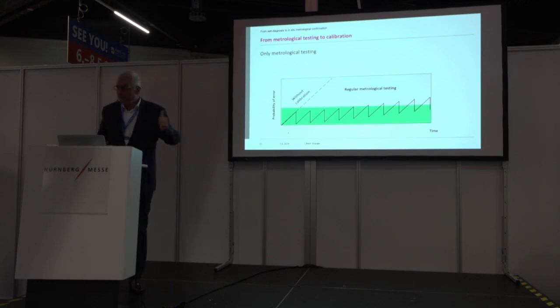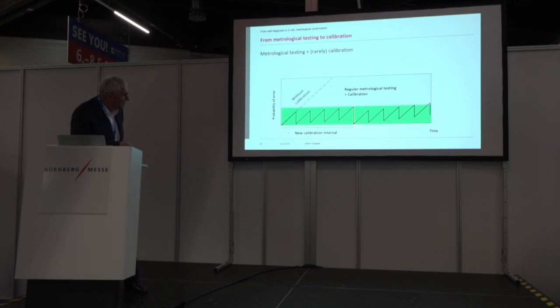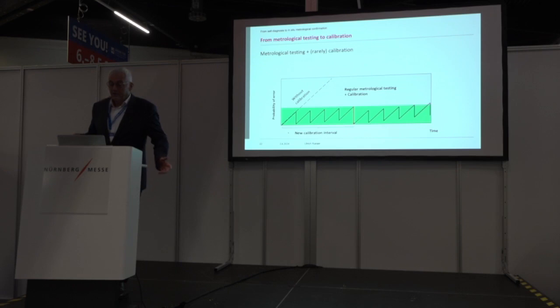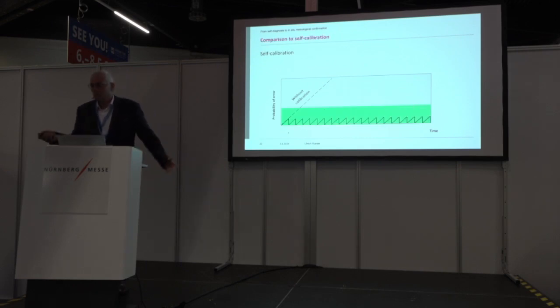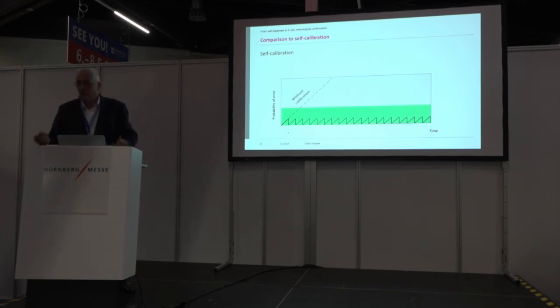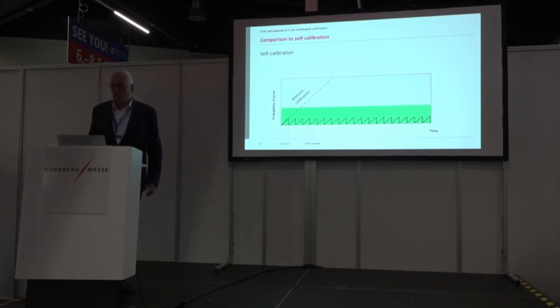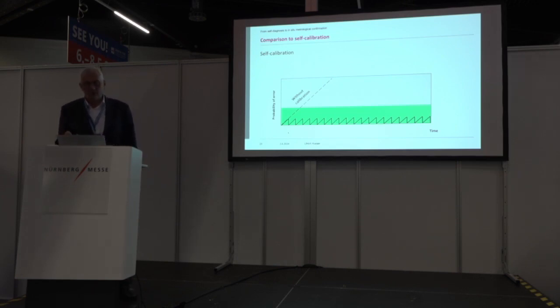In order to put it back to 0, I make again a calibration, but much more seldom. Then you have a new calibration interval, which maybe is 3 times, 4 times, 10 times the calibration interval we had before. When, on the other hand, you have self-calibration, it's easy. It works internally, tuck, tuck, tuck. You can do it every day, and it works forever without calibration. But as I mentioned, self-calibration is not available for all measurement methods.